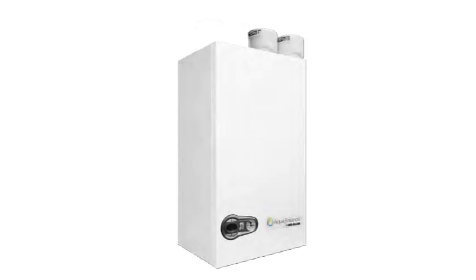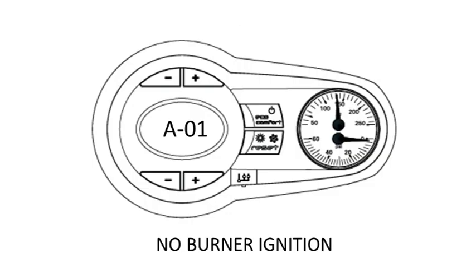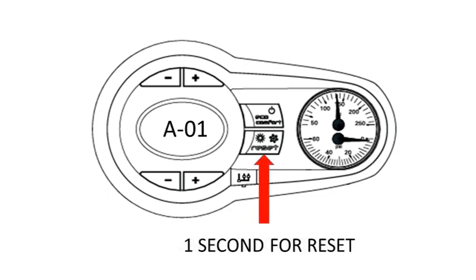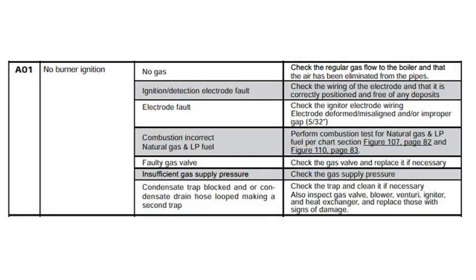For our AquaBalance boiler, the current fault will be listed on the screen either as a lockout code or a blocking code. The manual lockout codes need to be manually reset after the condition has been corrected by pressing the reset button for one second. The blocking codes will reset automatically when the fault is corrected. Use the manual to determine what the fault code means and how to correct it.